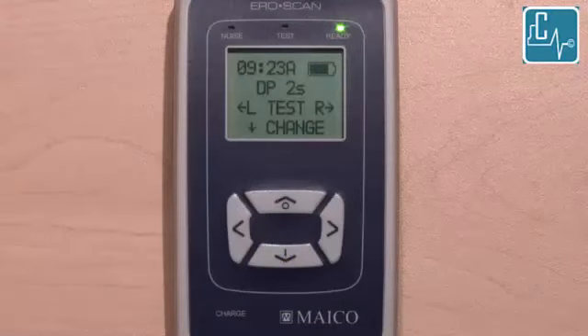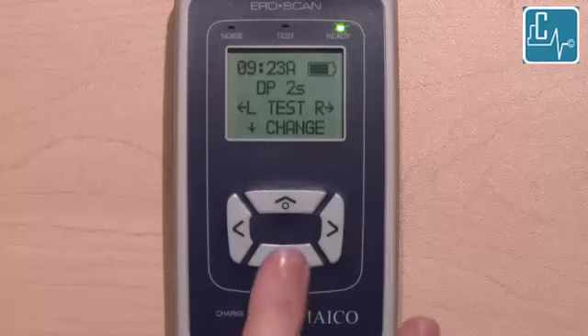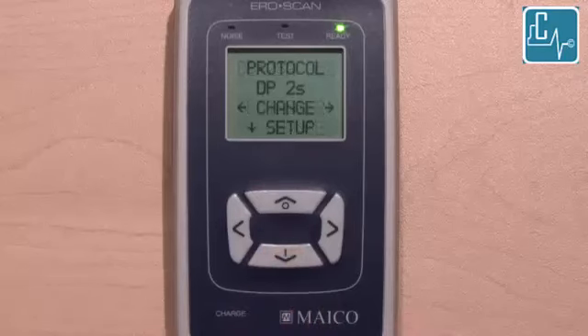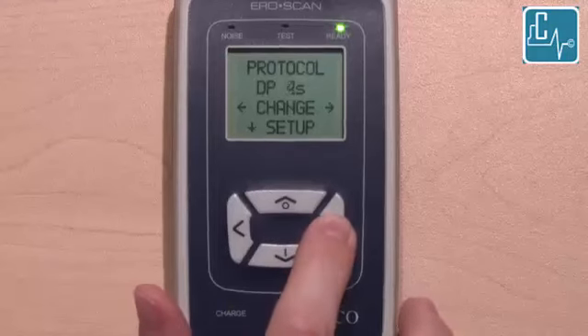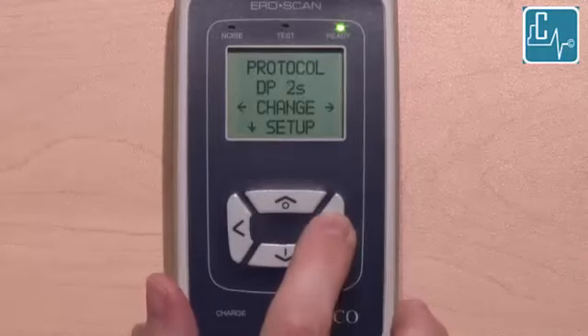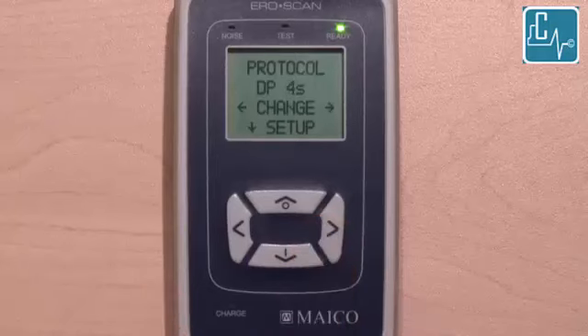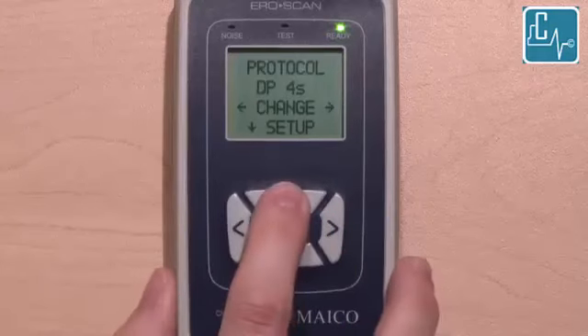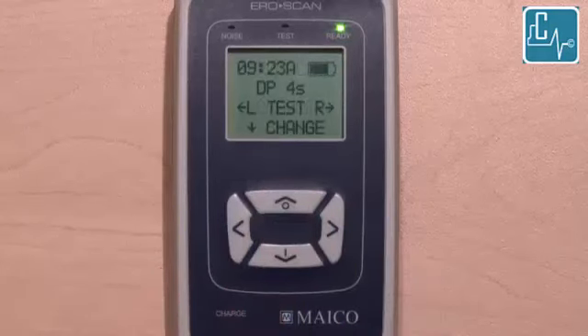To select a different test protocol, use the down arrow to select Change from the main test screen. Use the left or right arrow to scroll through the protocols available in the device. Once the desired protocol is selected, press the up arrow to return to the main menu. The new protocol will be displayed on the main test screen. Upon power up, the device will default to the last protocol selected.